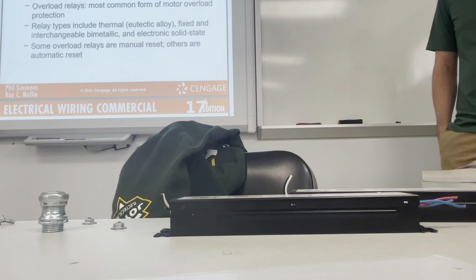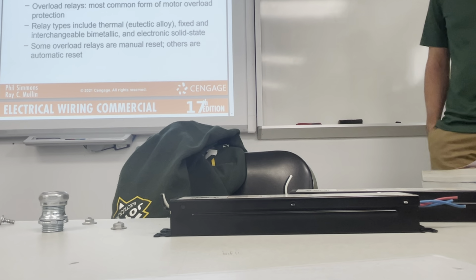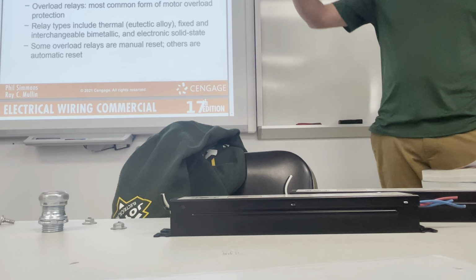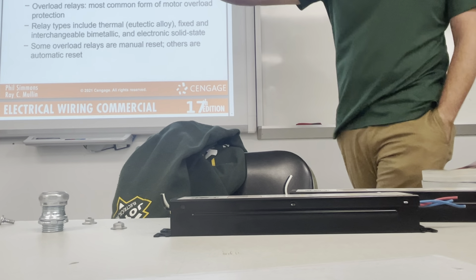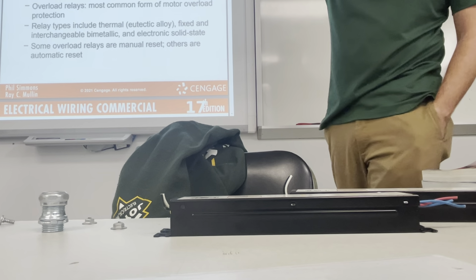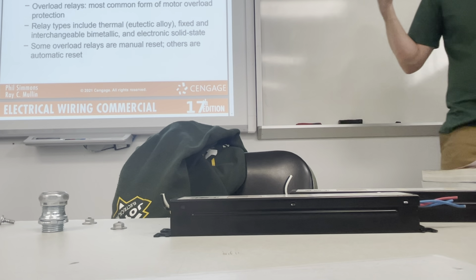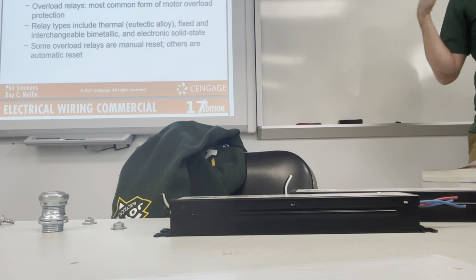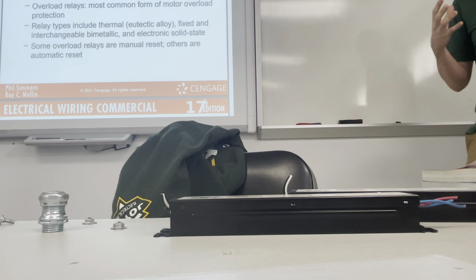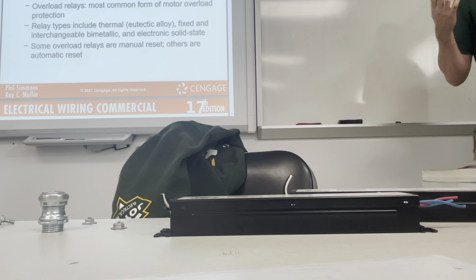Especially if you're in an old Scranton house, what happens? They flicker. They dim a little bit, right? Because that initial startup current is really high, and then it stabilizes back down to its normal 12.5 amps or whatever. Same thing with a three-phase motor. Can you imagine how much power and torque and current goes into starting like a 100, 200, 300 yard conveyor belt? Especially if just one motor's running it.